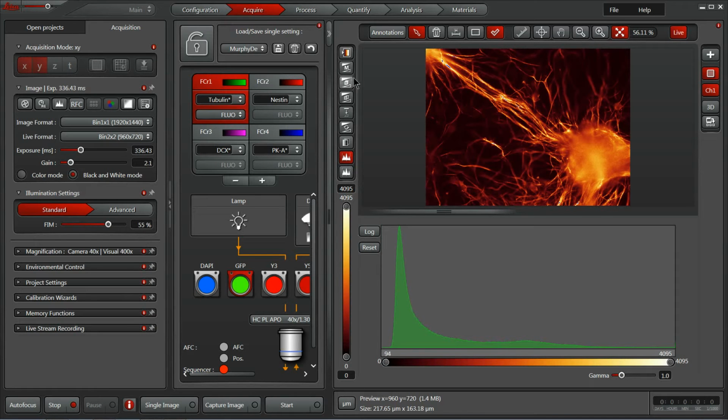Now let's look at the histogram in conjunction with my personal favorite way of setting my exposure time, altering the lookup table from a pseudo color of green or a raw grayscale into this heat map. So the heat map gives us the same information about our fill within each pixel using an easier to see variation of colors as it goes through our reds into oranges, yellows, and whites. Our eyes can pick out a little clearer the variation in intensity.